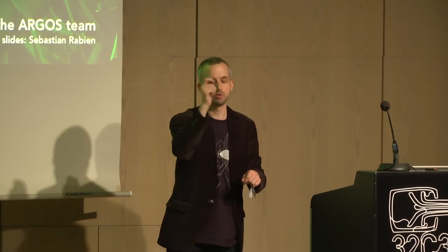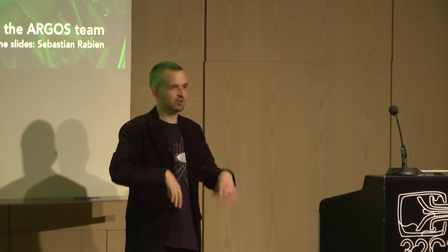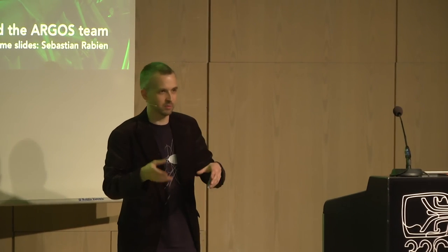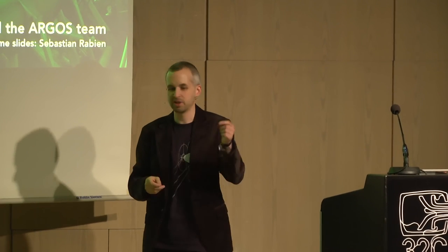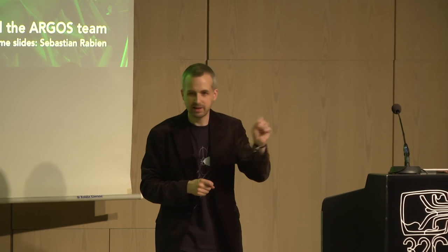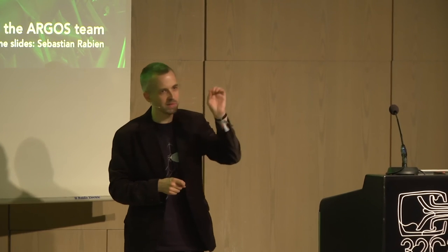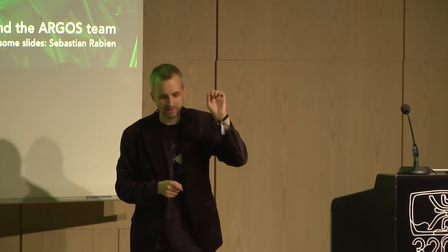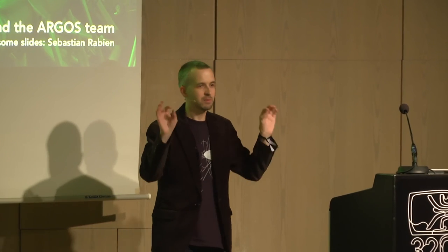They will, of course, look like, "Huh, what is this?" And that's not what we want, because then they might push some other buttons which they're not supposed to push. If you, of course, work directly at the system, you have to maintain it, you open it, you have to align the lasers and whatnot. Beyond their self-aligning capabilities, you do have to wear all these protective laser goggles, because if you don't, you do have instant eye damage. You might not see it instantly, but it's there instantly, period. So, really, folks, don't experiment on this laser stuff at home if you are not following basic laser safety rules.